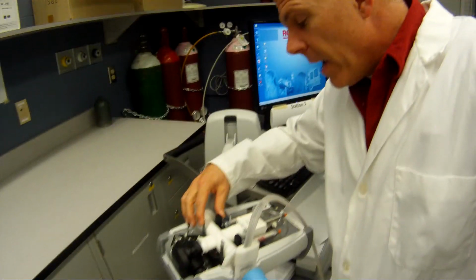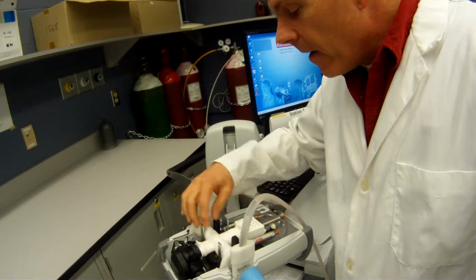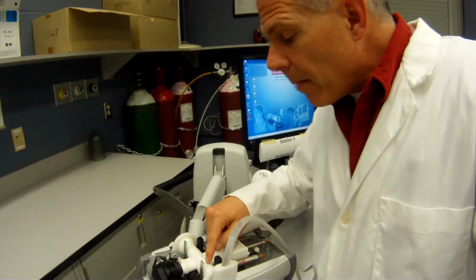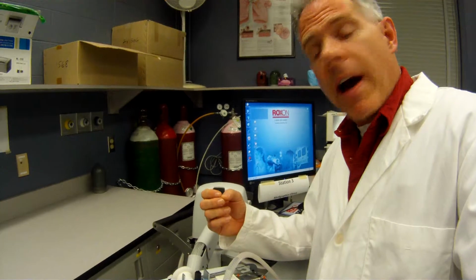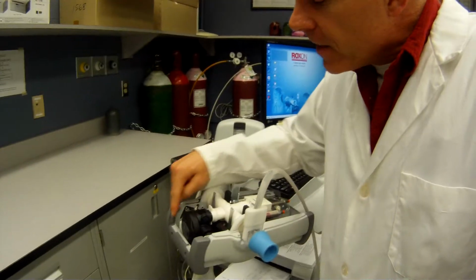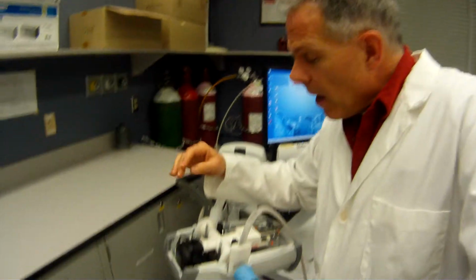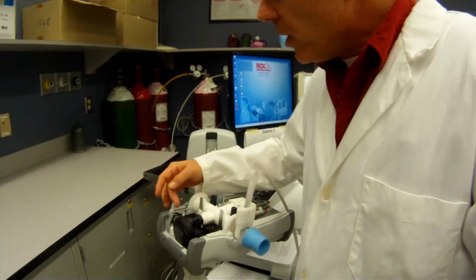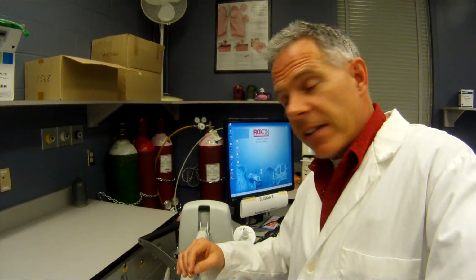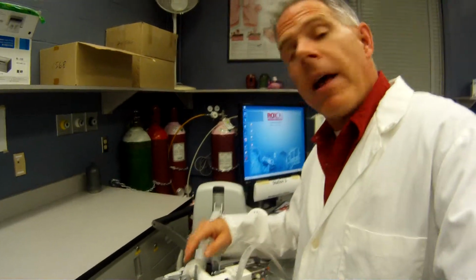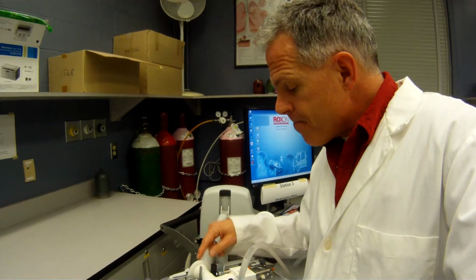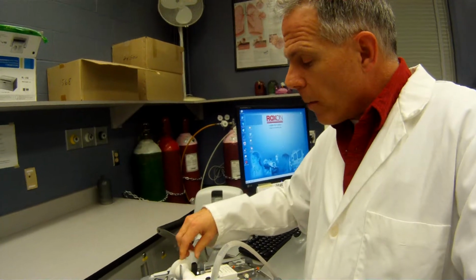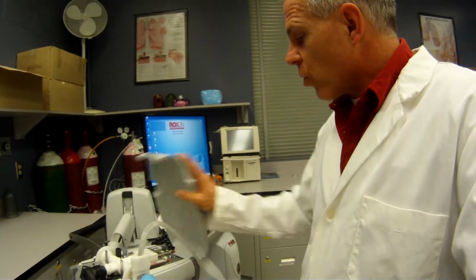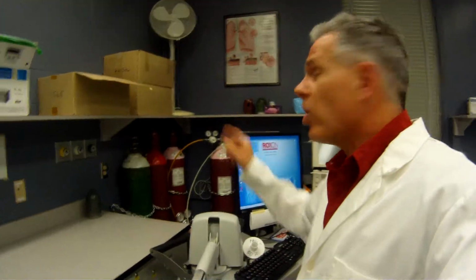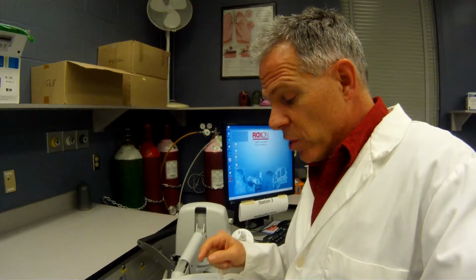Now you can see here it's got some little valves inside here and this little rubber piece. It's important to watch for that, because if this gets ripped, which it will do over time, you need to be able to replace that. This black piece right here is the regulator. That's what the patient will be breathing through when we do specific tests like the nitrogen washout or the DLCO test. Okay? So it's important that all these valves be working properly and that you're aware of how those hook up. So the fact that those are gas operated makes you realize that you need to have your gases hooked up for this device to work.